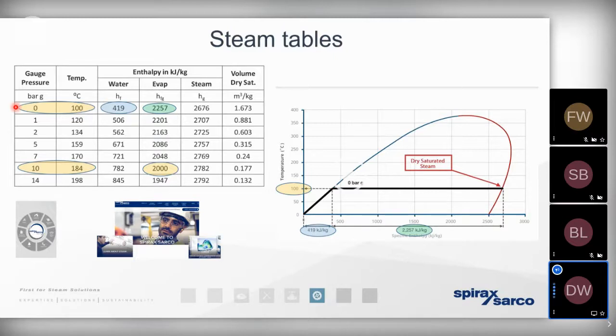But from an energy perspective, remember, the more condensate is given up to the distribution pipework, the greater the inefficiency. But because of the condensate that languishes in the distribution pipework, it's inevitable that the steam that finds its way to the process is going to be wetter. And the wetter the steam, the less energy there is contained within the steam. So as far as the process is concerned, for one, we get less energy being distributed to the steam, and we get a reduced mass of steam being distributed to the process, all as a result of us generating and distributing wet steam. So it's important to bear in mind that the steam tables, all the information that's shown on the steam tables here, is based on the understanding that the steam is in a very, very dry condition. Anything less than perfectly dry steam will result in a greater condensate load and less energy being present for the process.